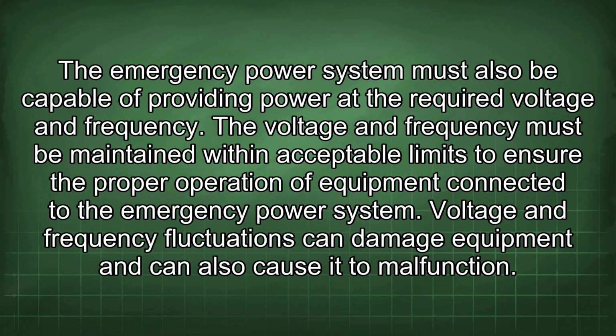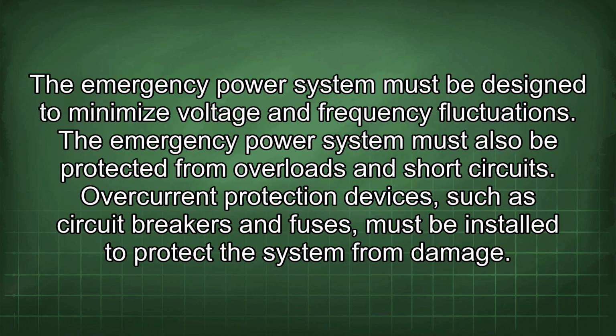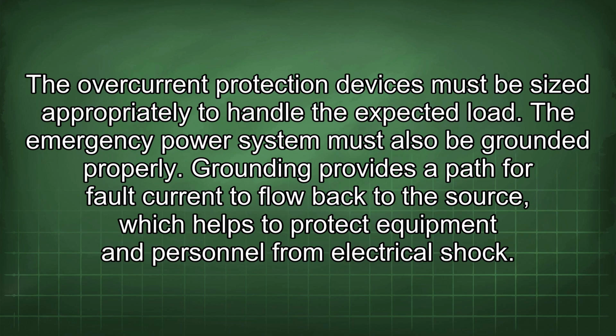The emergency power system must also be capable of providing power at the required voltage and frequency. The voltage and frequency must be maintained within acceptable limits to ensure the proper operation of equipment connected to the emergency power system. Voltage and frequency fluctuations can damage equipment and can also cause it to malfunction. The emergency power system must be designed to minimize voltage and frequency fluctuations. The emergency power system must also be protected from overloads and short circuits. Overcurrent protection devices, such as circuit breakers and fuses, must be installed to protect the system from damage. The overcurrent protection devices must be sized appropriately to handle the expected load.